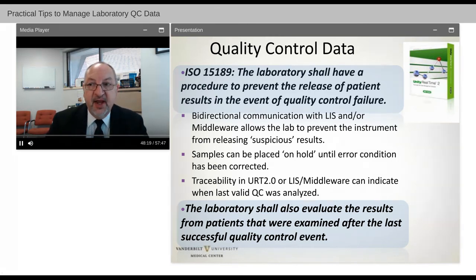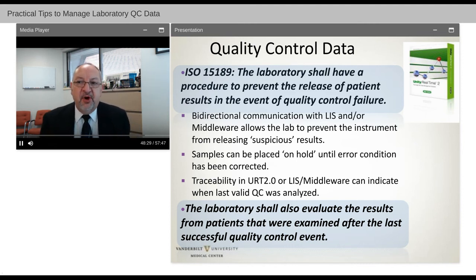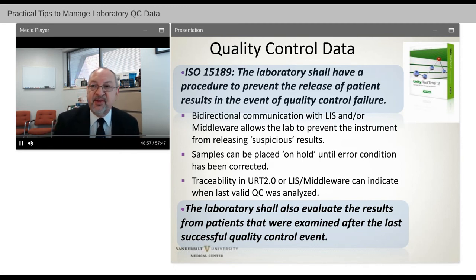Bidirectional communication with LIS, your laboratory information systems, and other middleware allows the laboratory to prevent the instrument from releasing suspicious results. You can place your samples on hold until the error has been corrected and troubleshooted, fix the analyzer and the method performance. You can also be traceable through your middleware to indicate when your last valid QC was added, help you in patient lookbacks. And the laboratory shall also evaluate the results from patients that were examined after the last successful quality control event. So programs like Biorad, Unity, Realtime can assist you in compliance with ISO regulations and even CAP and CLIA regulations in the United States.